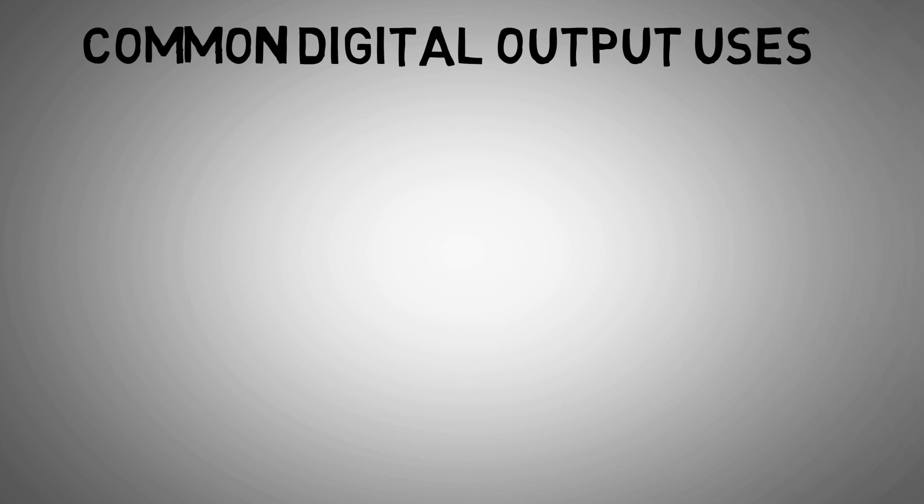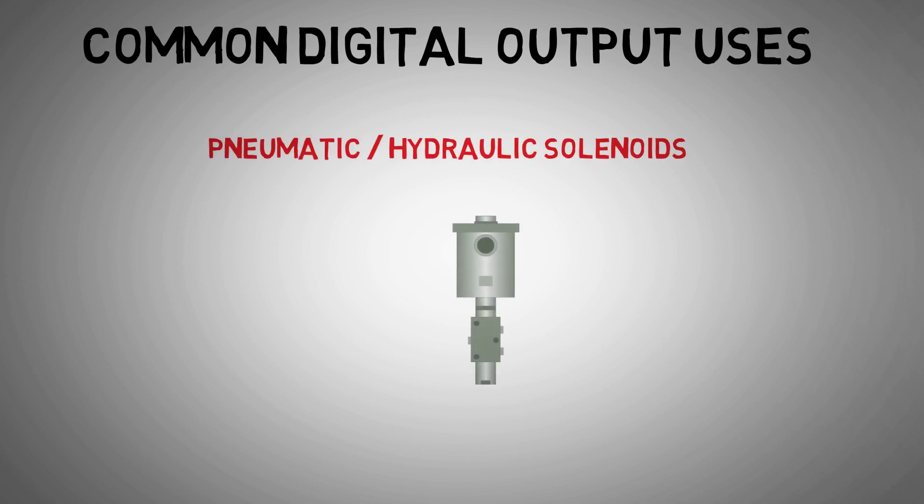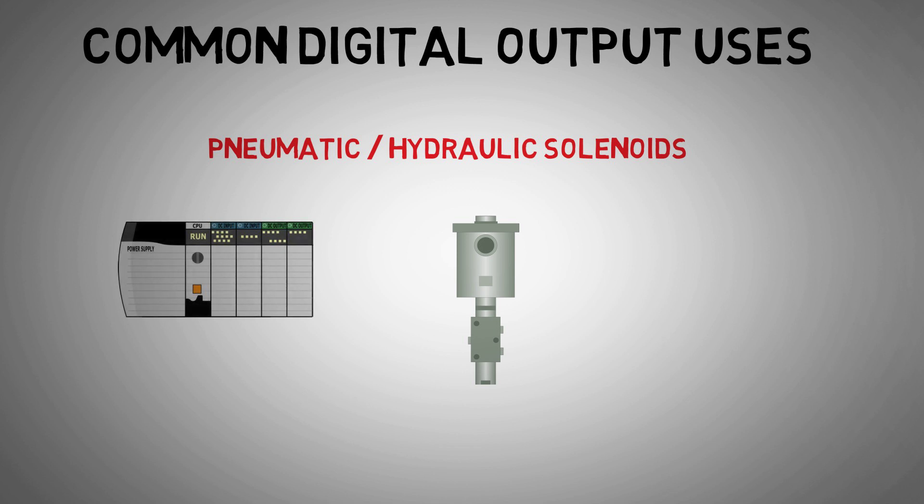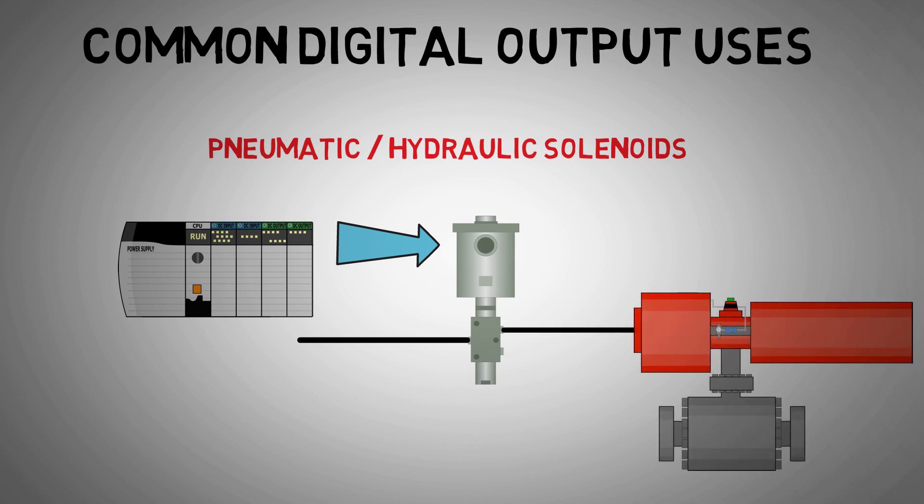Common uses for digital outputs include pneumatic and hydraulic solenoids. These solenoids are energized or de-energized by digital outputs and allow compressed air or hydraulics to flow through pipework, which moves cylinders in applications ranging from rams and lifts to process isolation valves.